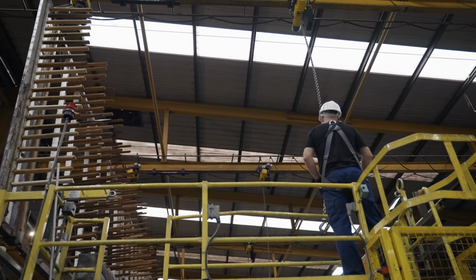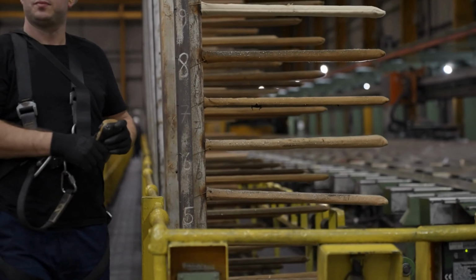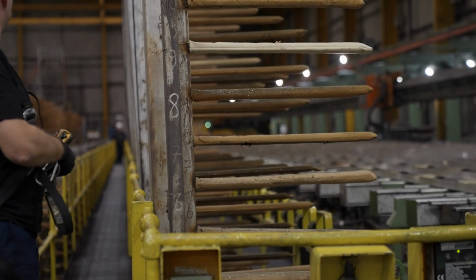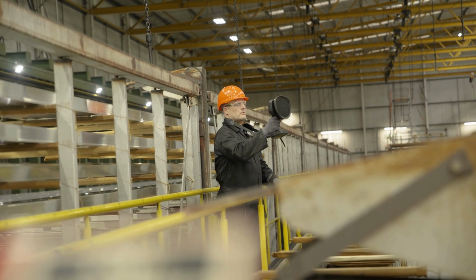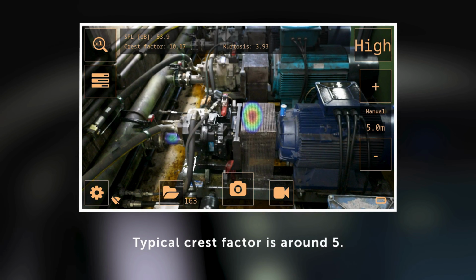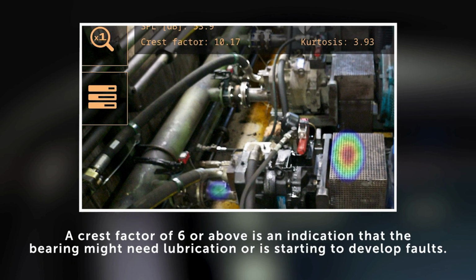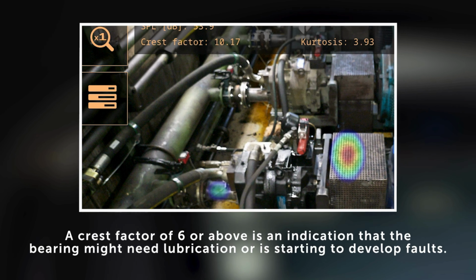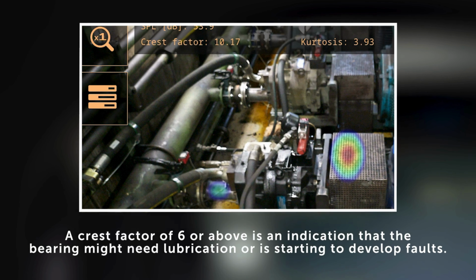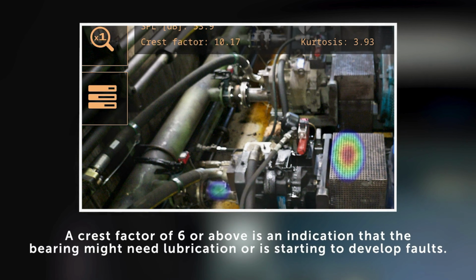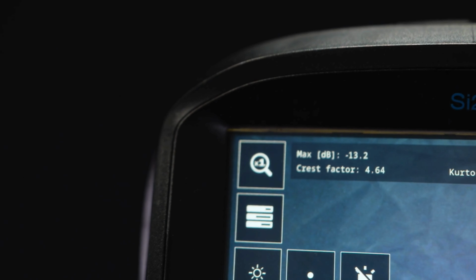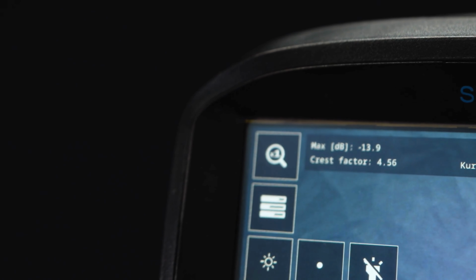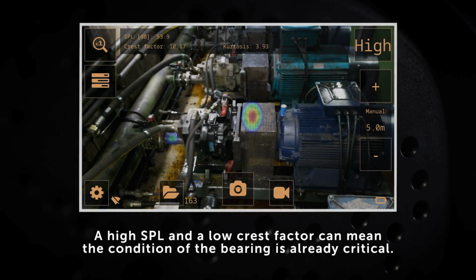Crest factor is a measure of the maximum amplitude in a signal compared with the RMS value. The crest factor of the sound signal from healthy bearings is typically around 5. If the crest factor is 6 or above, it is an indication that the bearing might need lubrication or is starting to develop faults. As the faults develop further, the crest factor will increase, but after a certain point, the crest factor might actually begin to decrease.